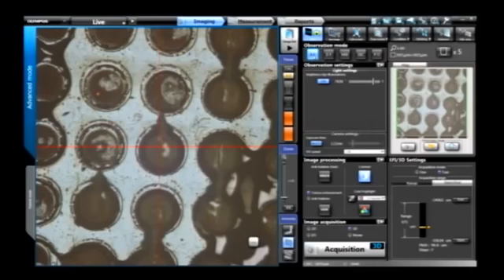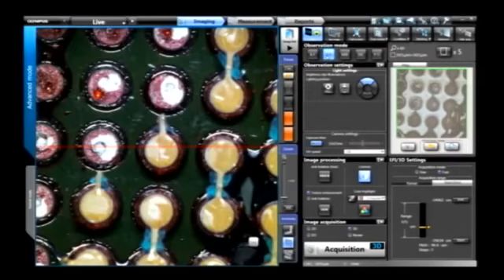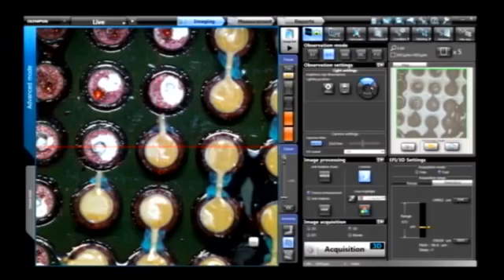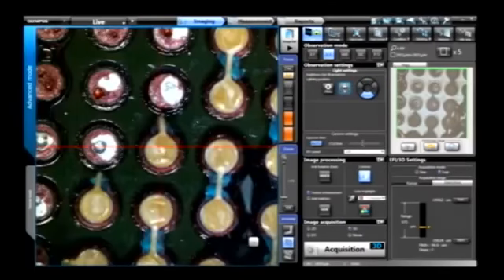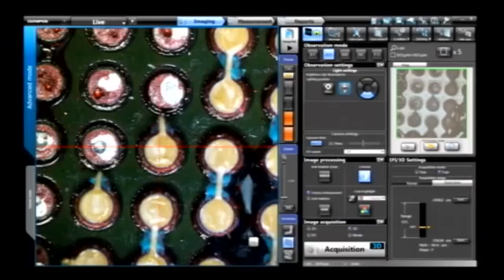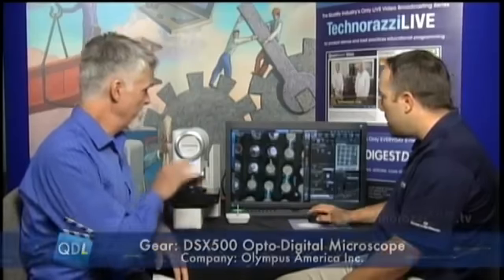So what we have on the image here is bright field. We can switch to dark field, and you can see that images come around. What's unique about this tool is we have a segmented LED dark field capability. This allows us to turn on different segments to light from different angles on your sample, and you can actually rotate those segments around to see lighting. It comes in different angles. So that'll help you choose what angle is best for what you're trying to image. Yeah, trying to image or trying to see different features or defects on the surface.